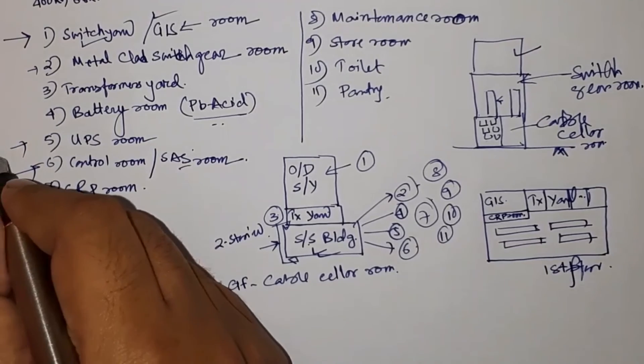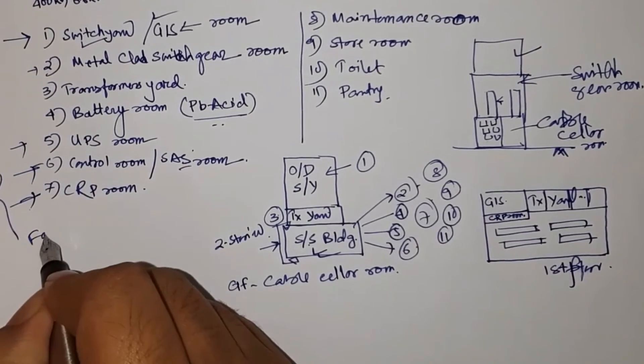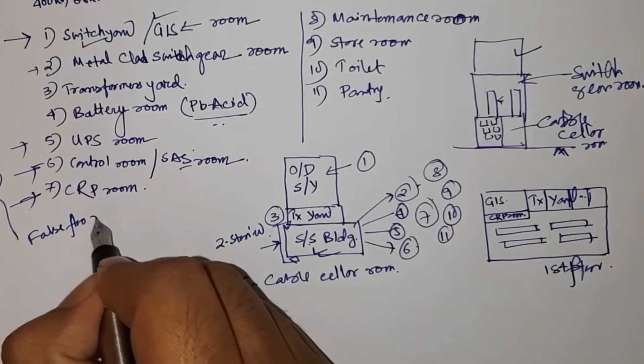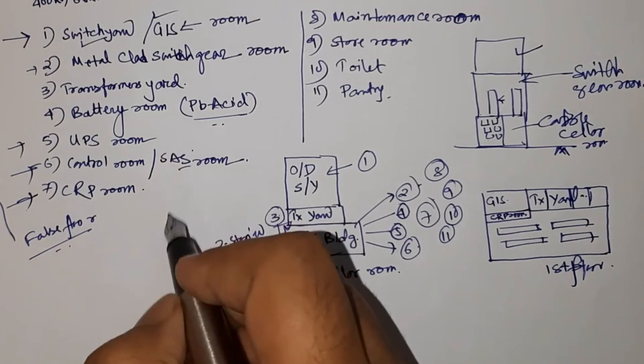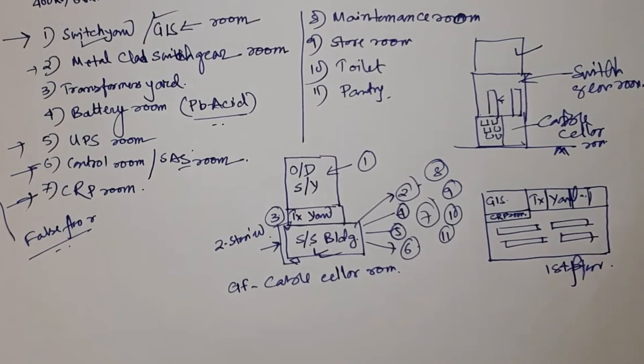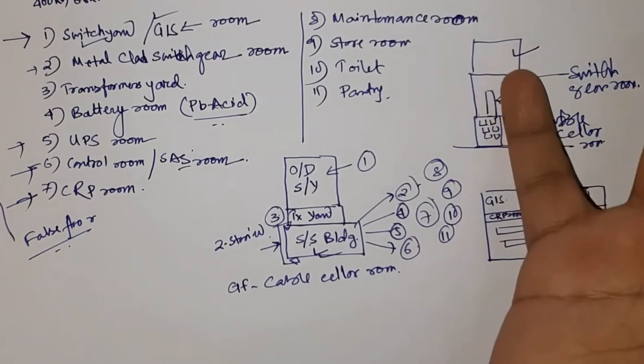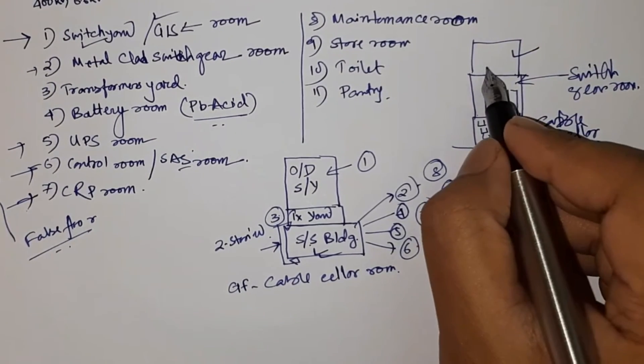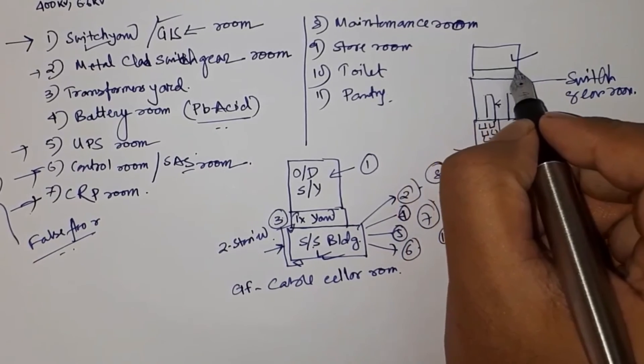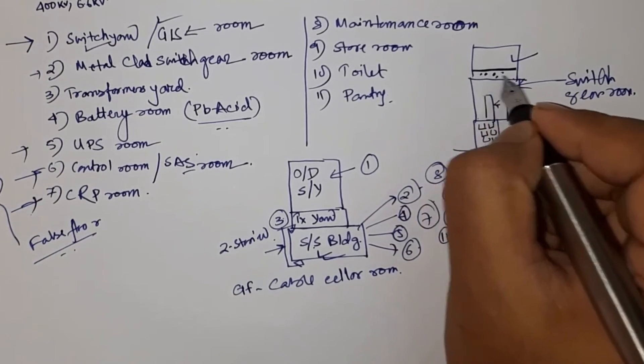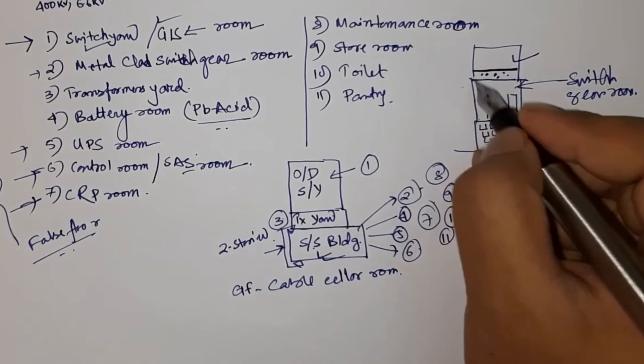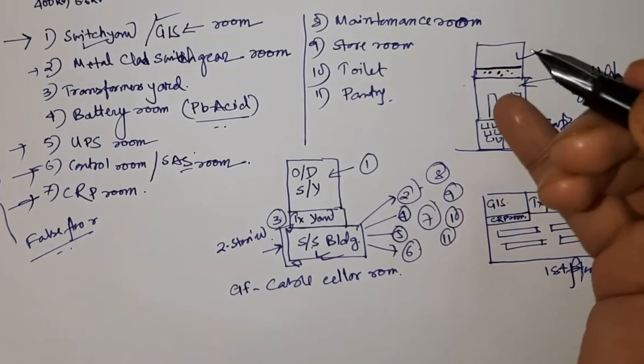Generally, the UPS room, control room, and CRP room are made with a false floor and false ceiling. The purpose of the false ceiling is aesthetic, while the purpose of the false floor is to allow easy cabling below the floor level, since these rooms are typically on the second floor. You cannot run cables easily through the structure, so you raise the floor — cables run below the false floor without affecting the architecture of the adjacent floor.